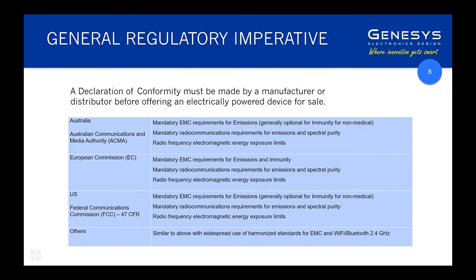Electromagnetic compatibility and radio communications compliance covers not just medical but any device that's electrically powered — essentially it has to meet regulatory requirements for EMC and radio communications compliance in terms of not interfering with other radio devices, and also human safety in terms of not exposing human beings to excessive levels of electromagnetic radiation. I find it quite amusing that this applies to Bluetooth and Wi-Fi, which are extremely low power, while people are perfectly happy to put a cell phone transmitting several watts against their ear next to their cranial cavity.